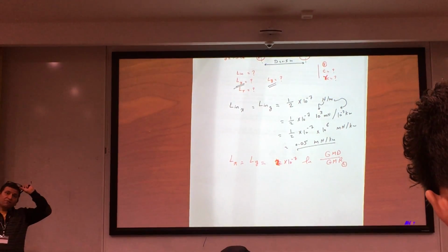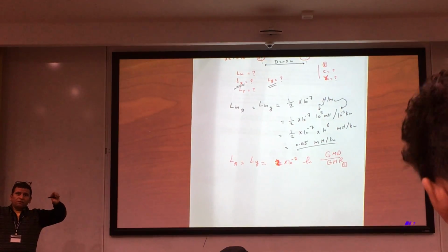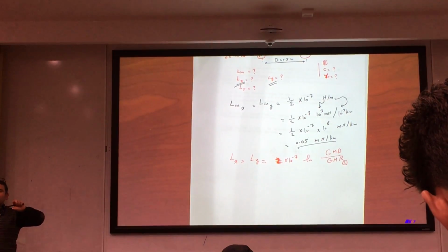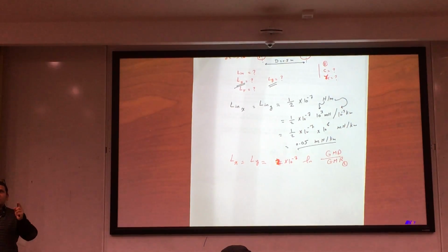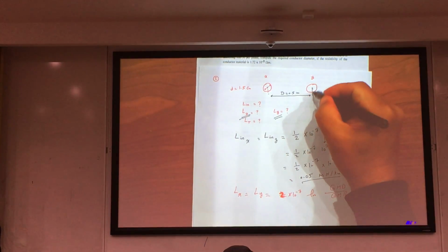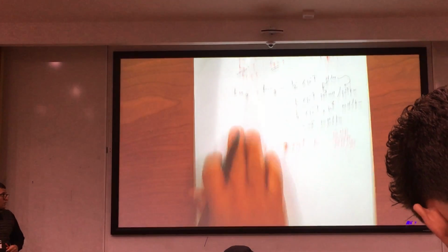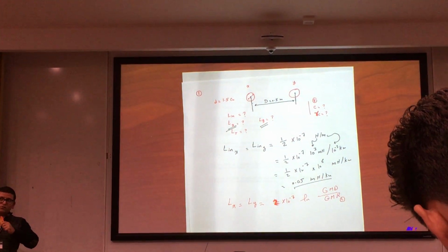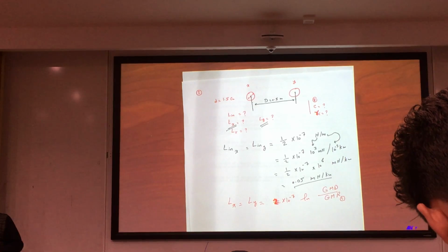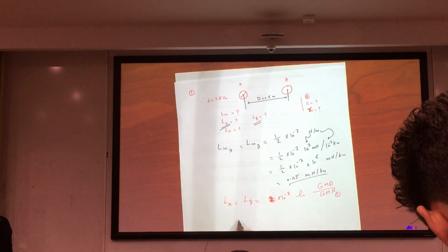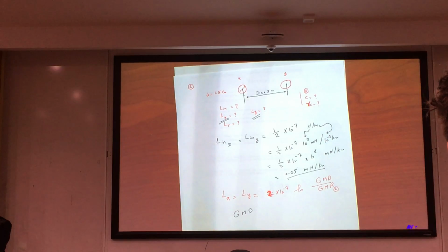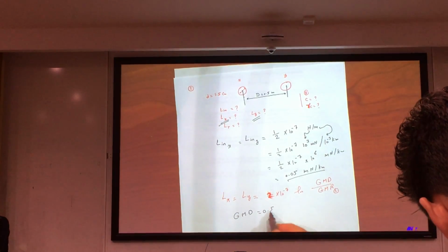So when we have two wires only made of solid conductors, geometrical mean distance is very easy, just the distance between centers. So in this configuration, geometrical mean distance is the distance between this center to this center here. So in single phase arrangement again, the geometrical mean distance can be calculated from the center of one conductor to the center of the other conductor. So GMD here is equal to 0.5 meters.